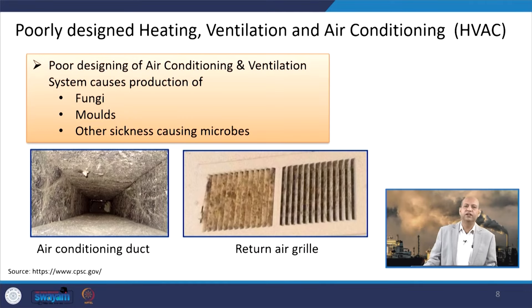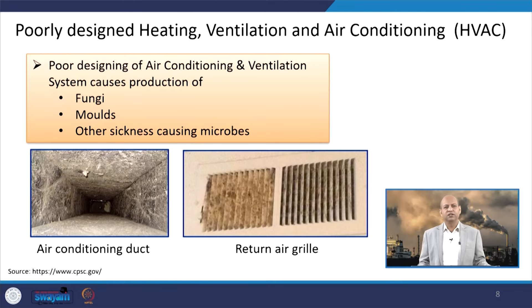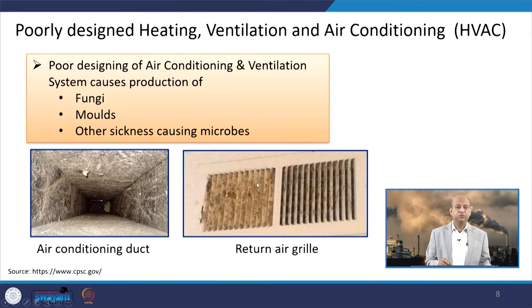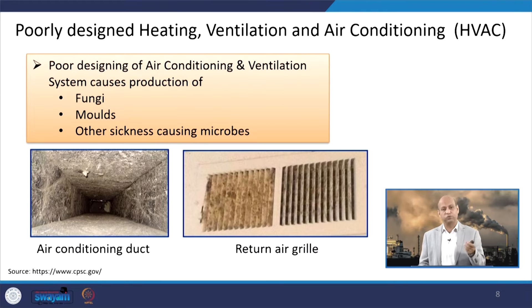A poorly designed HVAC — heating, ventilation and air conditioning — system can result in several kinds of pollutants, including fungi, molds, and other sickness-causing microbes or bacteria, adding to allergic-related health issues. If the air conditioning duct is not clean, is moist, and causes microbial activity, it is very dangerous to health. The return air grill, if not cleaned regularly and periodically, can itself become a source of air pollutants rather than improving air quality.